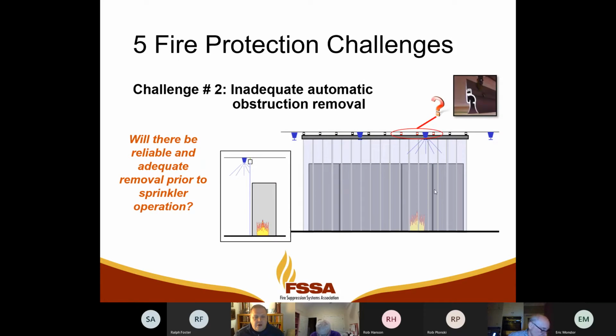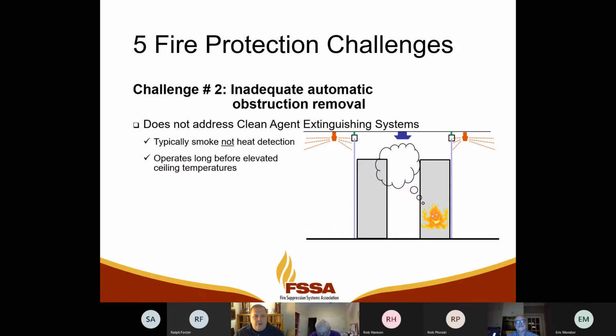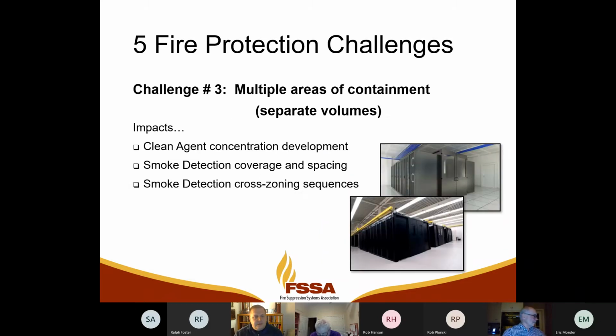So the question is, as you have these links and they're about 4 feet apart in most systems, how big a fire is it going to take for all of those links to fuse and that track to fall down to the ground and let the curtains fall there? Another thing is clean agents. Clean agents are meant to extinguish or activate early when the fire is small using smoke detection. Well, we're not going to be building up heat to the point that we can melt any of those links. So that methodology of using the fusible links doesn't really address clean agent systems.